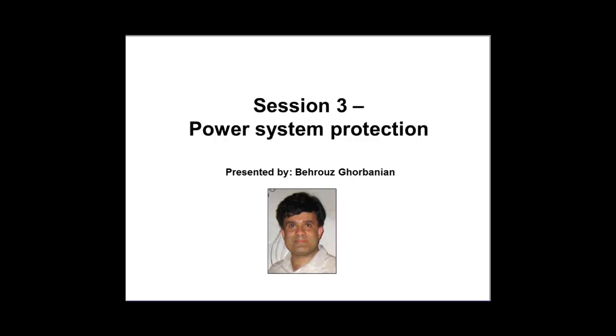Input of current, input of voltage. Do you know where that input comes from? Where comes the input of current? Where comes the input of voltage? The fuse again doesn't need that, but the relay does need that. Have you ever heard about CT, or current transformer? Have you ever heard about VT, or voltage transformer? So these things are required for relay protection, but they are not required for fuse protection.